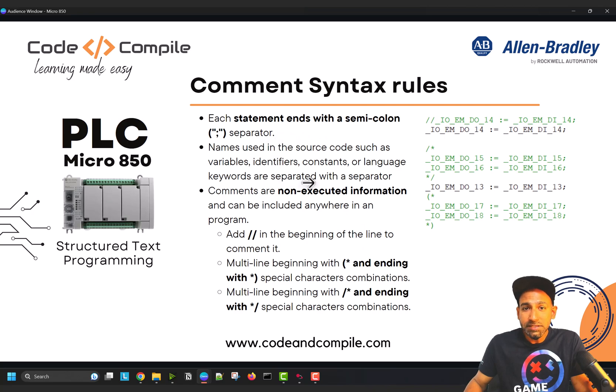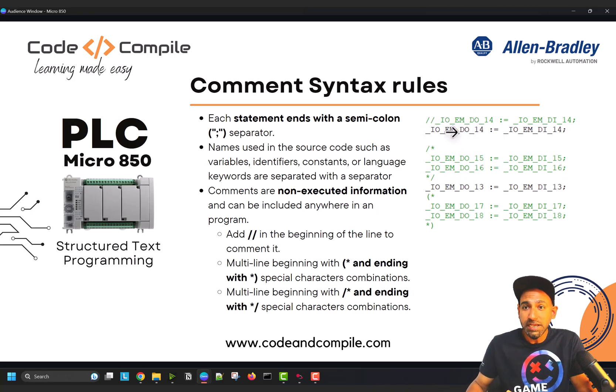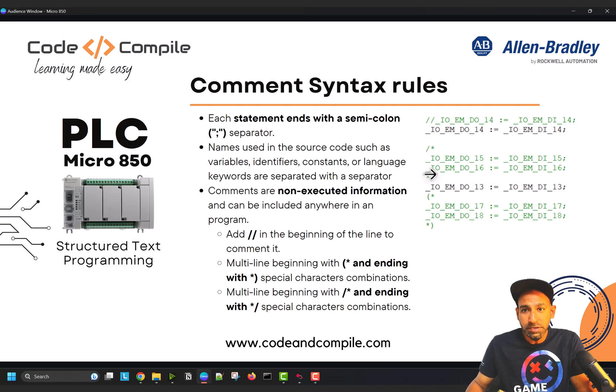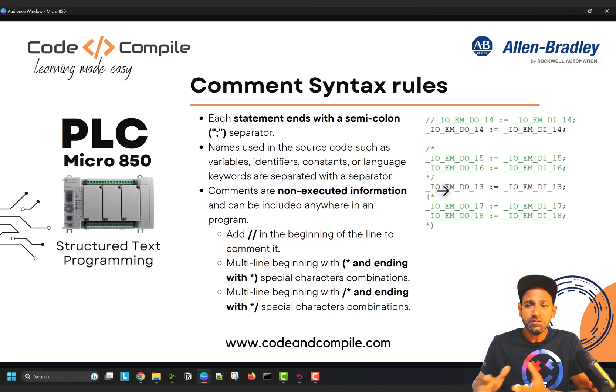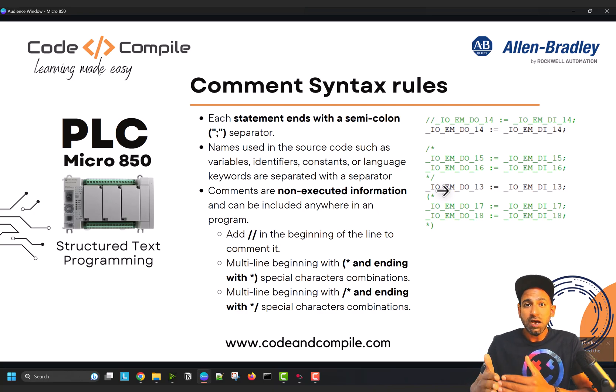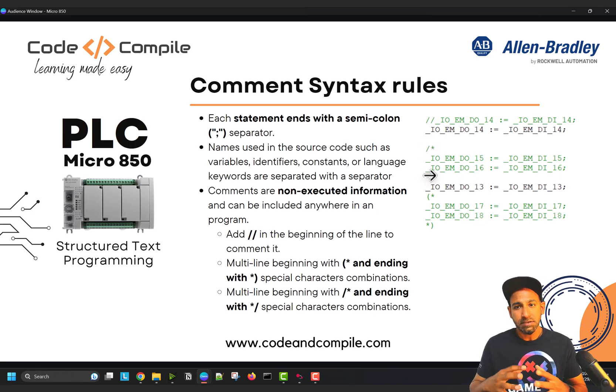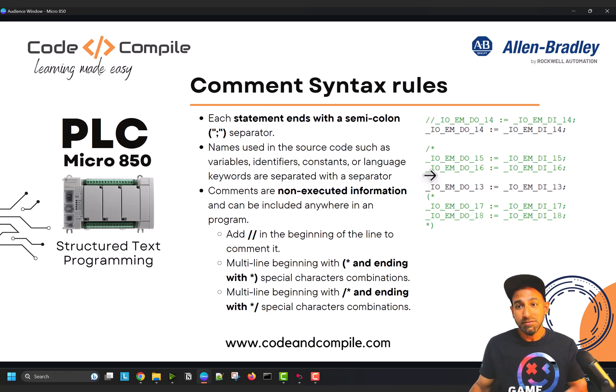There are some rules: for example, you can't use names that are reserved for keywords, identifiers, or constants — we will study that in detail. In the editor, green color is how comments look, and black is the real statement. You can also change the colors. You can also use an open bracket with a star for a multi-line group comment. This is important because when you want to debug your program and see the effect of a particular statement, instead of deleting it, you can just comment it out — whatever is in a comment will not be executed by the PLC. This we don't have in Ladder Logic and FBD.